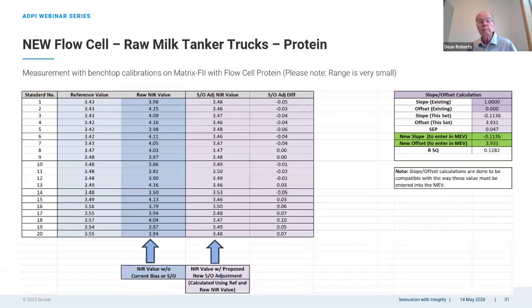And then here's the protein. Now this actually looks pretty reasonable. And just as a point of context, the reason that we didn't do protein in the first study on the pilot skid is the results just didn't really change enough for us to make any decisions about whether it was working or not. It's kind of like doing a single point bias adjustment. It's right at one point, but you don't know if it's right at the rest of the points. But here we were measuring the protein, and you can see that it's got a pretty reasonable repeatability and comparison to the benchtop values that we used as the reference lab for these measurements. Next slide, please.